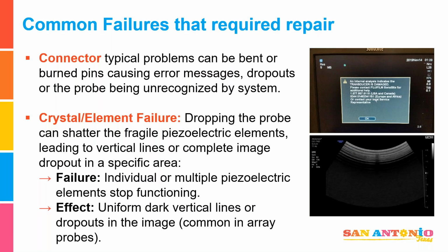Stop. Look at your probe, look at the connectors, and if either one of them is damaged, don't plug them into that port. Get either the probe or the port fixed. The worst case I had was replacing that board - a horrible job. If you haven't done a scan head select board on a 22, it takes probably 2-3 hours if you know what you're doing. Then I had to replace 4 probes because they kept plugging into a bad board until they finally ran out of probes and couldn't use the machine. I'm like, well, you could have stopped after the first probe.